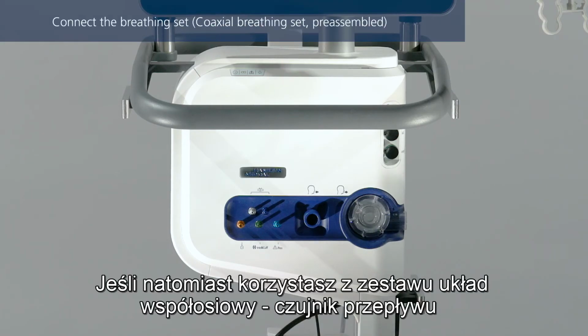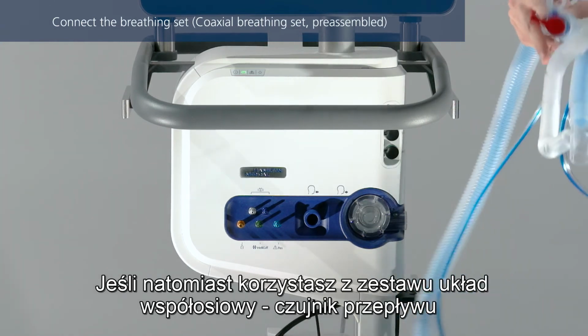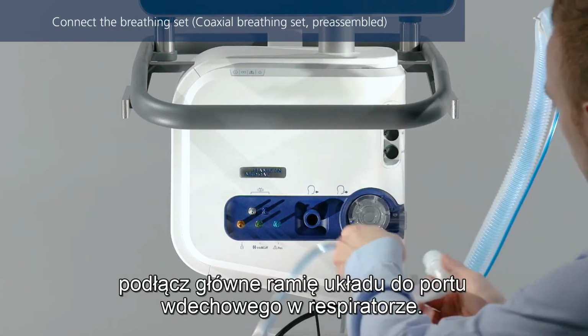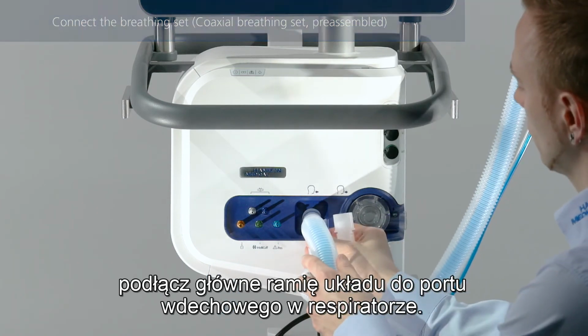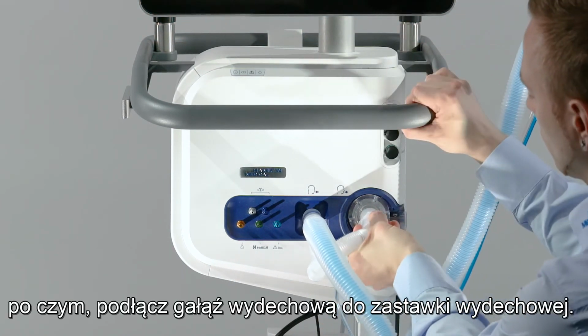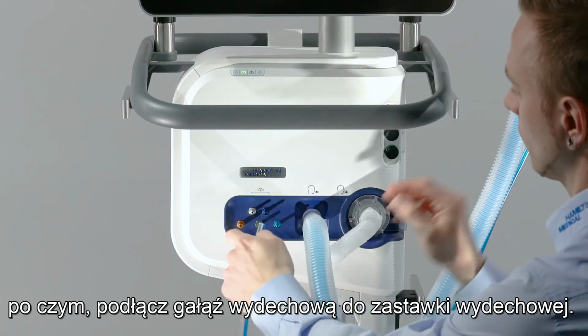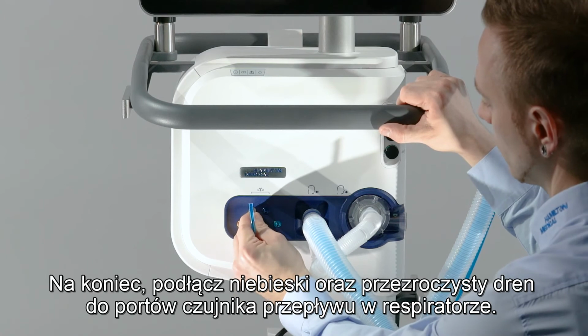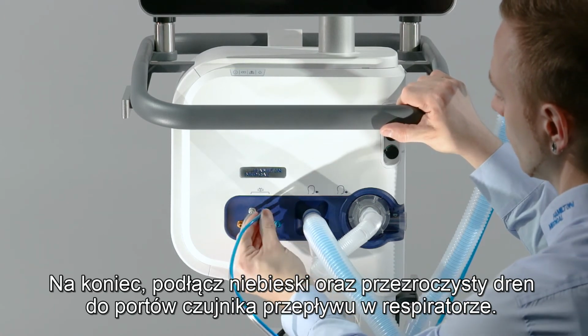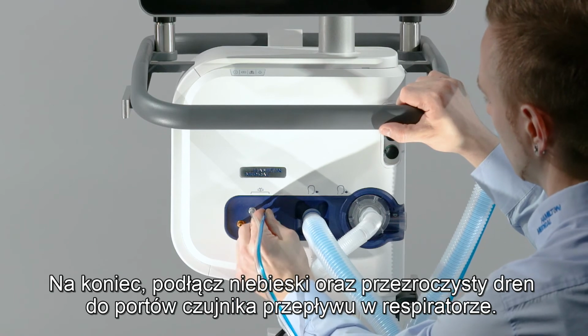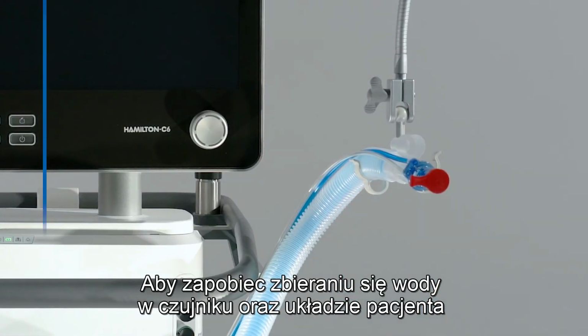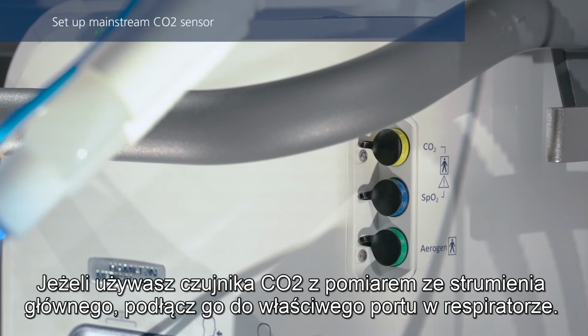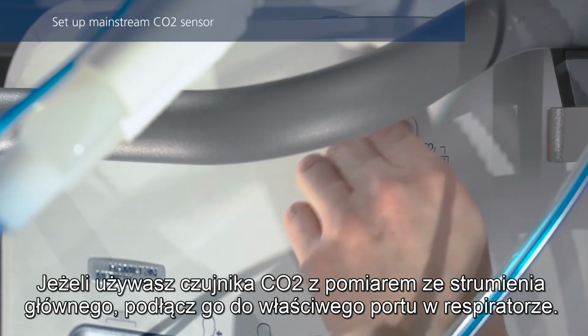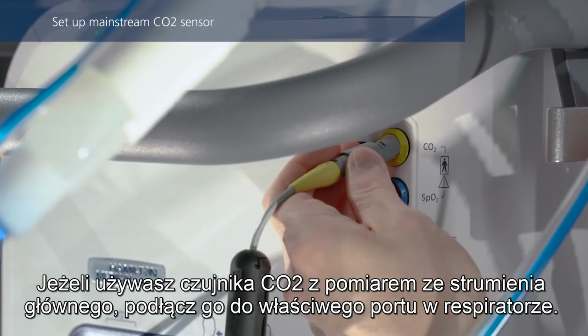If you are using a coaxial breathing set with the proximal flow sensor, first connect the main tube to the inspiratory port on the ventilator. Then, connect the expandable expiratory tube to the expiratory valve. Finally, attach the blue and clear tubes to the flow sensor connection ports on the ventilator. To prevent water accumulating in the flow sensor and tubing, position the flow sensor tubing on top of the flow sensor. If you are using a mainstream CO2 sensor, connect it at this point to the corresponding connection port.